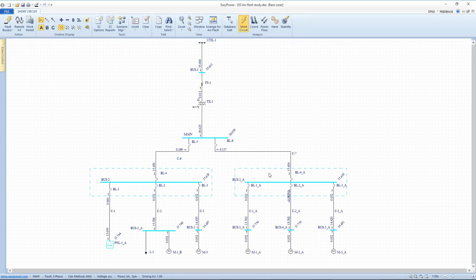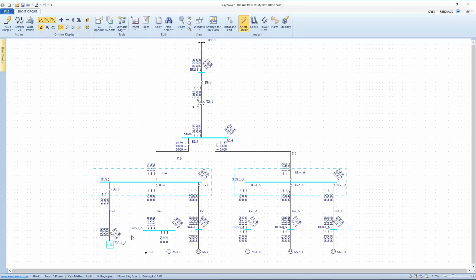So we'd fault all the buses. Again, we get nice colors, nice numbers, and these are showing us, in line with the cable, each branch current contribution. On the oblique is the total fault current, which will include contributions from all sources. And since we have motors downstream, we can see that the motors during the first half cycle are contributing to the current for that fault. If we look at 5-cycle and 30-cycle numbers, so this will be the current at 5 cycles into the fault, the one thing that's changing is the motor contribution. For small motors, at 5 cycles, the contribution is pretty much faded away. And certainly for 30-cycle faults, all motor contributions have pretty much been eliminated.